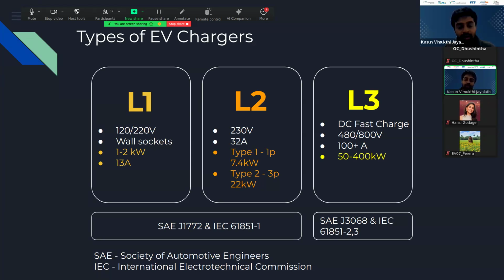The other type of charger is the L2 charger. They have two separate connection types depending on utility connection: single phase and three phase. If your location has three phase, you can use the three phase option which delivers 22 kilowatts to the vehicle. If you only have one phase, it delivers 7.4 kilowatts. The maximum current rating that can be handled by type 1 and type 2 connectors is 32 amperes, which is the maximum level according to the connector standards.